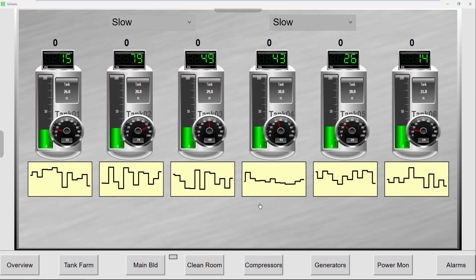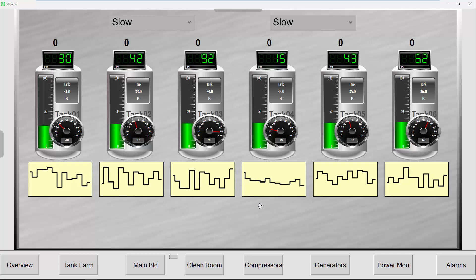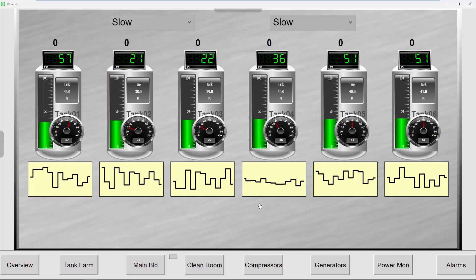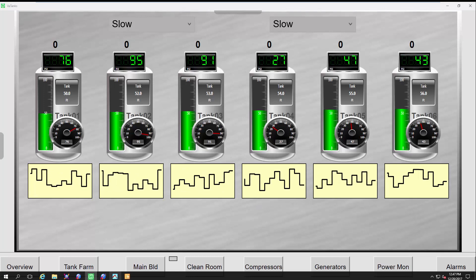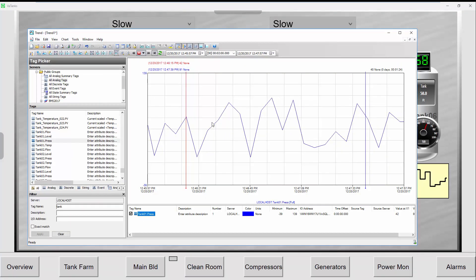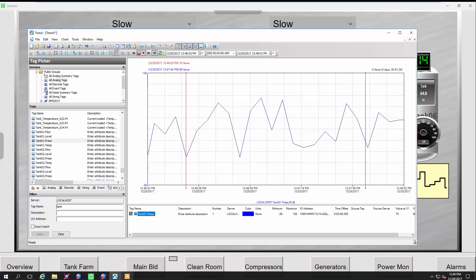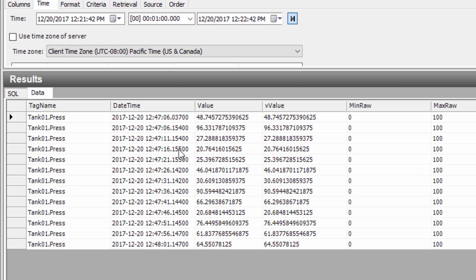As you can see on the screen, I have an InTouch OMI application running with six tanks. I'm using a little thumbnail trend on the bottom of each tank showing the resolution of data going into the Wonderware Historian. If I go look at my historian client trend tool, you can see the resolution of the data being pulled directly from the Wonderware Historian. In the query tool, I can see data coming in about every five seconds - the slow pull mode is set for five seconds.